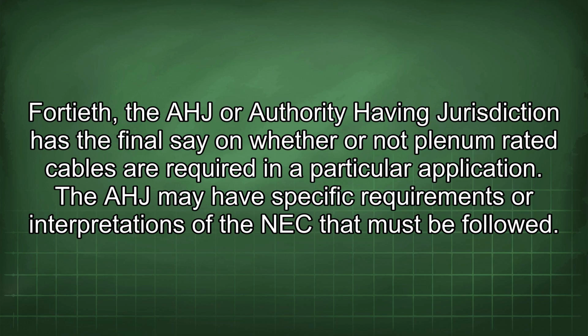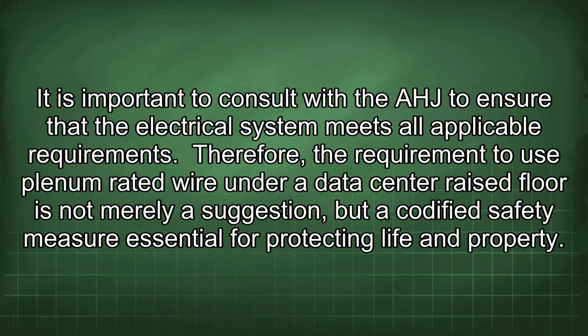40th, the AHJ, or authority having jurisdiction, has the final say on whether or not plenum-rated cables are required in a particular application. The AHJ may have specific requirements or interpretations of the NEC that must be followed. It is important to consult with the AHJ to ensure that the electrical system meets all applicable requirements.